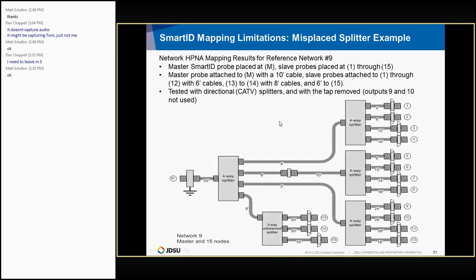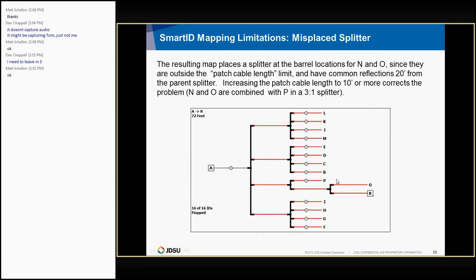The misplaced splitter example here: a couple of these probes were connected out with, I don't know, a 10-foot cable or something like that. They had a long cable length on these two, longer than the rest of them. So this cable length extended out beyond the patch cable length, and it allowed it to pick up an extra splitter here. But if you increase that patch cable length to 10 feet or more, then those two points out there, right here, show up as part of this splitter as a 3-to-1, which is the correct mapping.